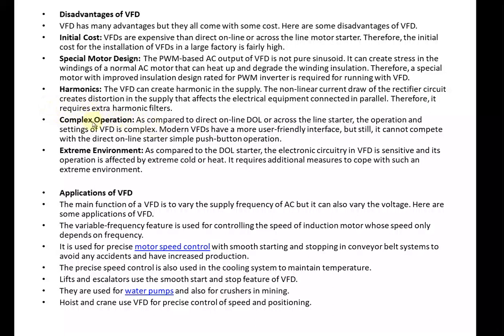Due to the non-linear current drawn from the rectifier circuit, harmonics create a distortion in the supply which can affect electrical equipment connected in parallel, so extra harmonic filters are required. Operation is complex — it cannot compete with the simplicity of a direct-online starter or simple push-button operation. Also, the circuitry in VFDs is sensitive and its operation is affected by extreme cold or heat, so additional measures are required to cope with the environment.